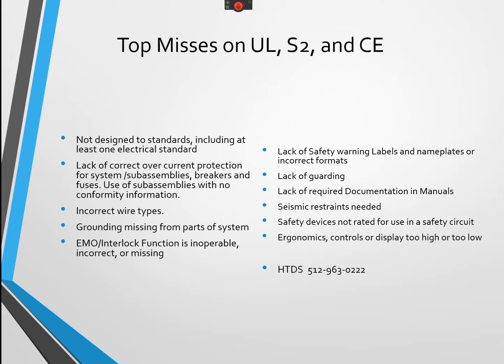And there are other very specific requirements for overcurrent protection at your power inlet, overcurrent protection for heaters and other devices, and also overcurrent protection for any convenience outlets. Those need to be GFCI protected as well. Generally, how we look at this is we try to find conformity information on the subassembly that says how it should be protected. If we don't find that, then we have to use the load data and other calculations to determine that. Using the correct overcurrent protection is going to get your product to market much faster.